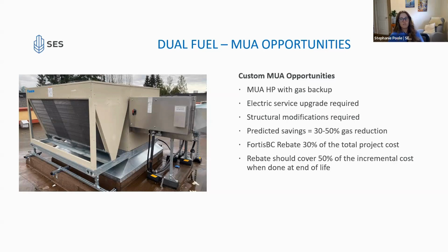So they are going to save between 30 and 50% gas reduction. Again, because they are using 100% outdoor air, they can't operate down to quite as low temperatures, and so they're not going to see as much savings as that rooftop unit, which can mix the air, and so it can go down much, much colder. There are Fortis rebates available for this. They won't cover the full incremental cost between like for like and a makeup air unit heat pump. They'll cover about 50% of the cost, depending on how many other upgrades were required.